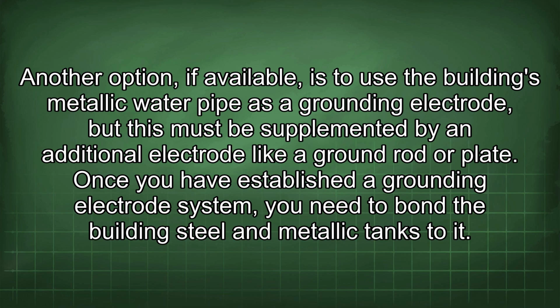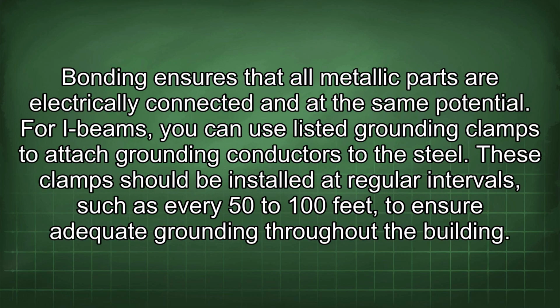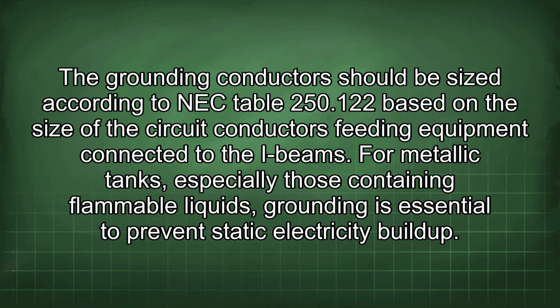Once you have established a grounding electrode system, you need to bond the building steel and metallic tanks to it. Bonding ensures that all metallic parts are electrically connected and at the same potential. For I-beams, you can use listed grounding clamps to attach grounding conductors to the steel. These clamps should be installed at regular intervals, such as every 50 to 100 feet, to ensure adequate grounding throughout the building. The grounding conductors should be sized according to NEC Table 250.122 based on the size of the circuit conductors feeding equipment connected to the I-beams.